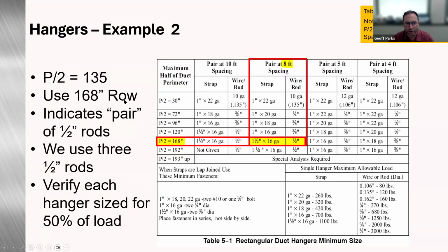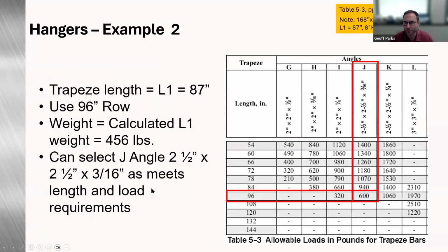So we used our L1 to define our P2. And now we're using that L1 dimension, which was 87, to now size the trapeze bar. So we would come to table 5-3, using our 87 inches, coming over to the trapeze length. We have to use 96 because that's the first one that's not less than the 87.